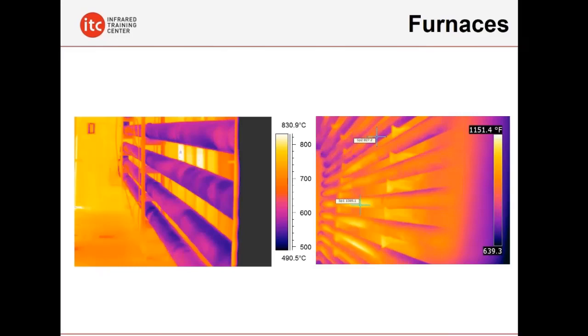In large industrial furnaces, we have a situation here with these furnace tubes, which can be carrying crude oil or perhaps water that we're turning into steam. These tubes can get coated with a slag that will build up. This sort of scaling that can happen on these surfaces can affect the efficiency of the furnace. Coking on the inside of these tubes can also affect the structural integrity of these types of devices. You can have catastrophic failures that can also occur. IR is utilized in this situation, a type of mid-wave thermal imaging system that can actually see through flame, to better diagnose these problems before they become big headaches.